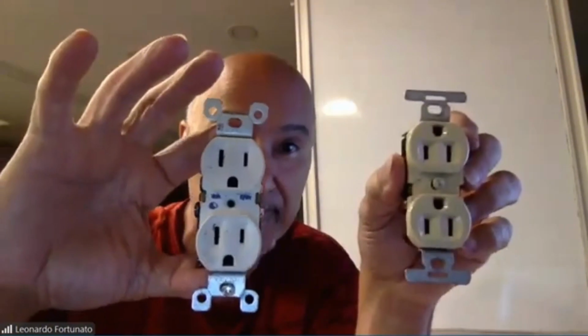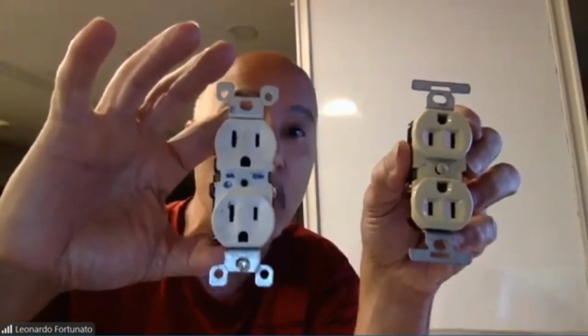Here's a simple thing I want to bring to our attention. Over here in Ontario, for the most part, it doesn't matter when you're installing a receptacle if you put it with the ground downwards or with the ground upwards. There's no code in a residential environment that says this is right or that is right. You can put them in any direction you choose. But most electricians, including myself, like to put our receptacles in this orientation - kind of looks like an inviting face.